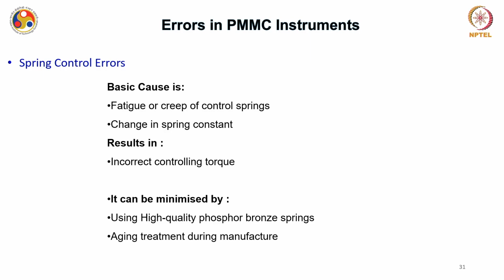Okay, so then the third kind of error is the spring control error, and the basic cause is the fatigue or creep of the control springs. Okay, and this will basically result in incorrect controlling torque, and when you have incorrect controlling torque, the meter may not come to its original position in the stipulated time, and because of that you may get a good amount of error in your measurement, which may be far away from the actual readings. Okay.